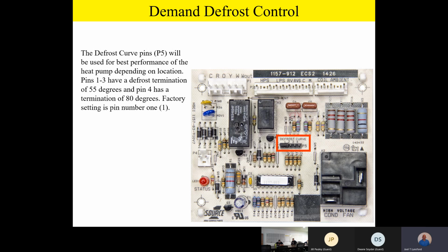So our recommendation is, even though you have a termination point of 55 degrees, the optimal curve for each tonnage will be at the factory setting. So if you have to replace a defrost control board, make sure to observe where the pin settings are on the defrost control board for optimal operation.